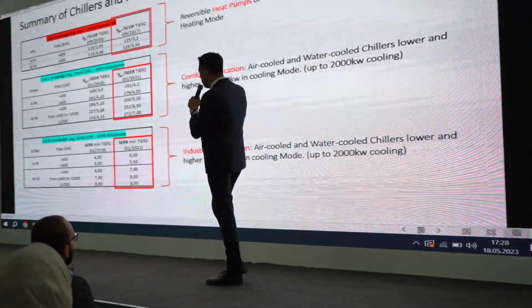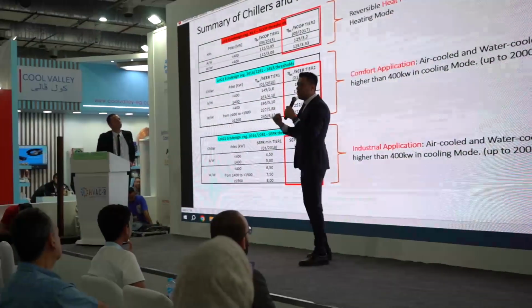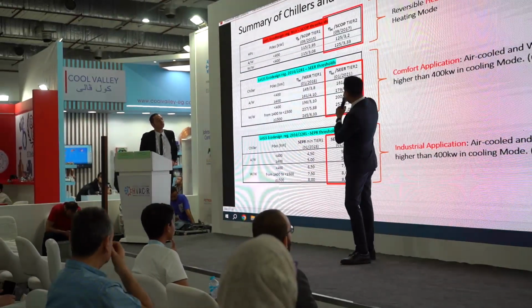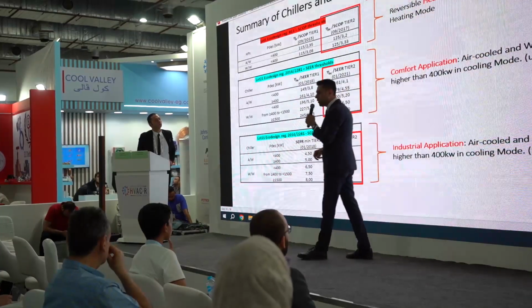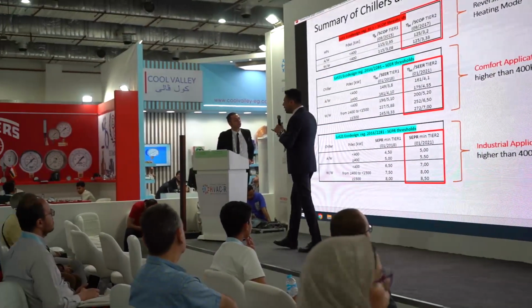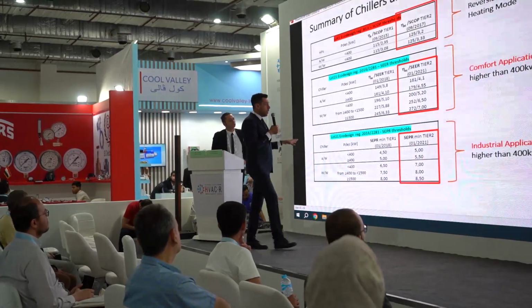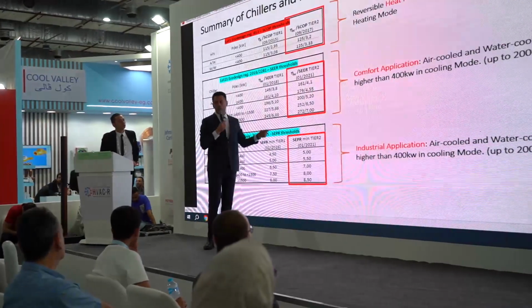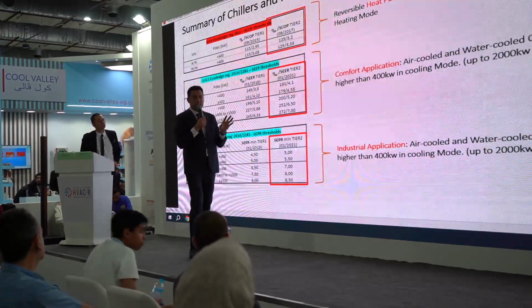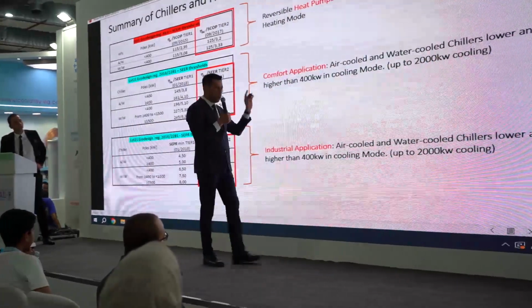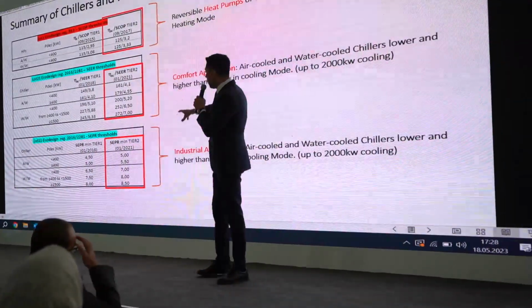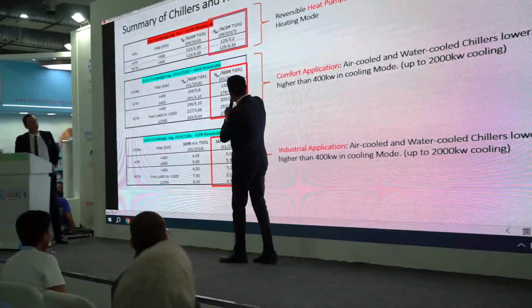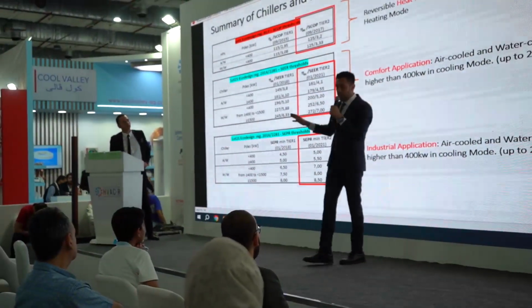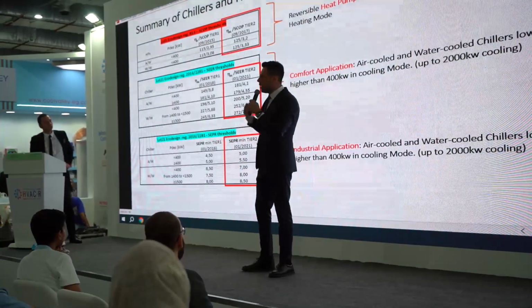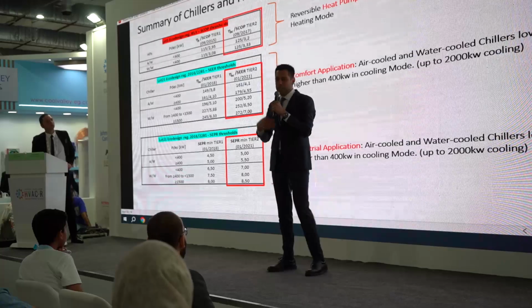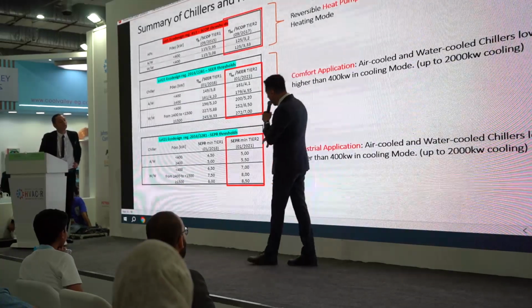New ETA value, new seasonal energy efficiency. Chiller 1000 kilowatt, 1300, 400. Minimum seasonal energy efficiency has to be 4.55. And also the chiller energy efficiency level for the tier 2 SEPR process, meaning industrial projects, not hotels, not commercial, industrial application up to 2000 kilowatt, you will be coming across better numbers. You see, for comfort chillers the big one is up to 4.55, but the industrial chillers, because they are running year round, 365 days, 24/7, have to have higher energy efficiency.